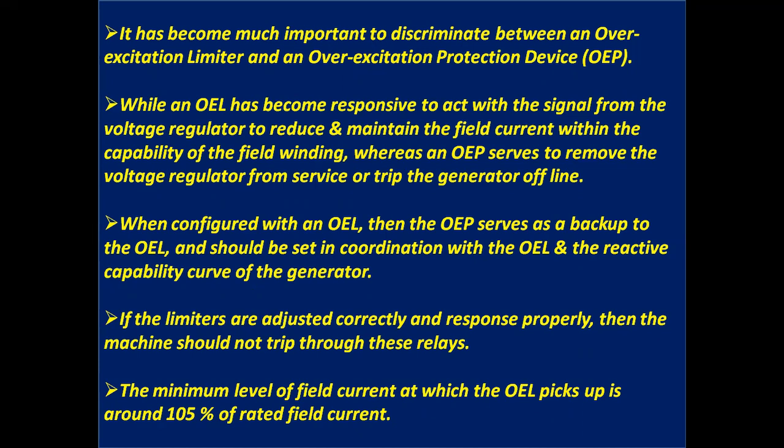When configured with an OEL, the OEP, that is overexcitation protection device, serves as a backup to the OEL, that is overexcitation limiter, and should be set in coordination with the overexcitation limiter and the reactive capability curve of the generator.